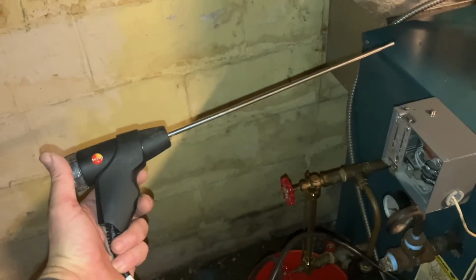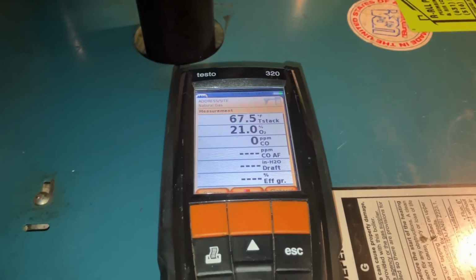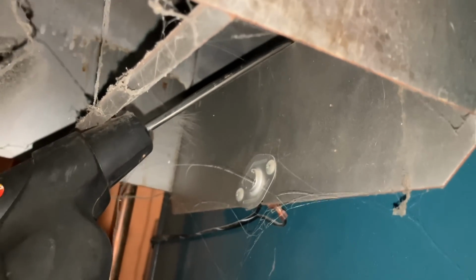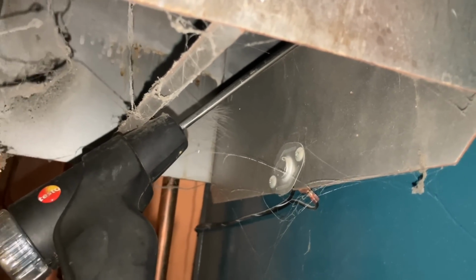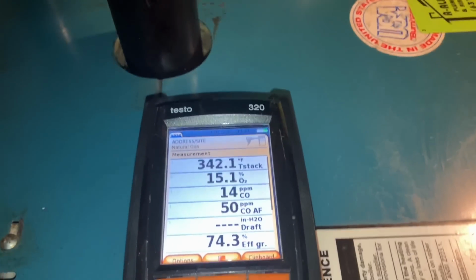All right, ready to get probed? It's that time. The Testo has been running. This probe is going up there, and conveniently it just wedges right in there. There's no designated hole, but it should be in the middle, inside top of the boiler before the exhaust gases mix with this air from the bottom of this draft diverter and go up the chimney. And we'll have some numbers.